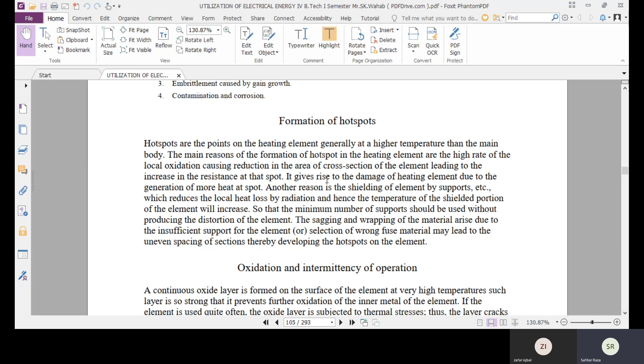The sagging and warping of the material arise due to insufficient support for the element, or selection of wrong fuse material may lead to the uneven spacing of sections, thereby developing the hot spots on the element. So in the formation of hot spots, the first reason is local oxidation, and the second reason is the shielding of the element by supports. Because of these two reasons, the formation of hot spots takes place.